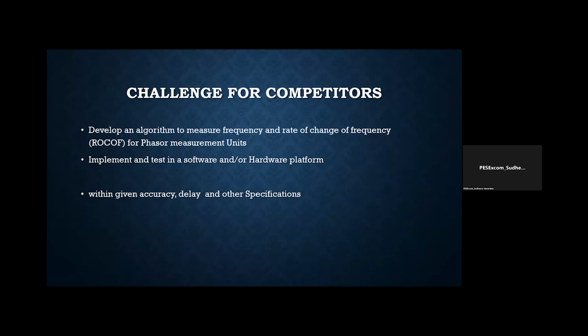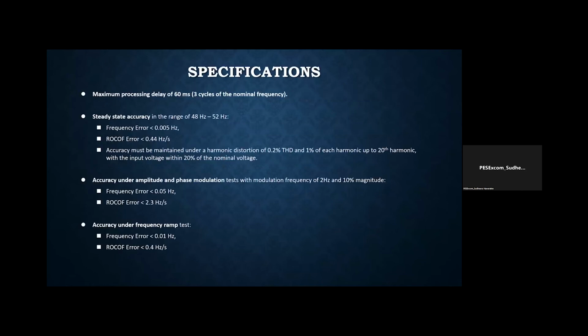For example, the specifications include a maximum processing delay of 60 milliseconds - meaning within 3 cycles of the nominal frequency, you have to give the values of frequency and rate of change of frequency, updating every 3 cycles or less. So the maximum processing delay is 60 milliseconds, and the steady state accuracy of the frequency and rate of change of frequency should be within a given value.